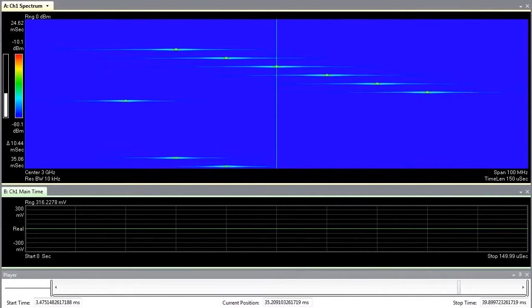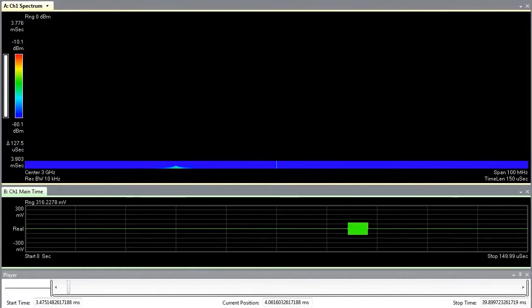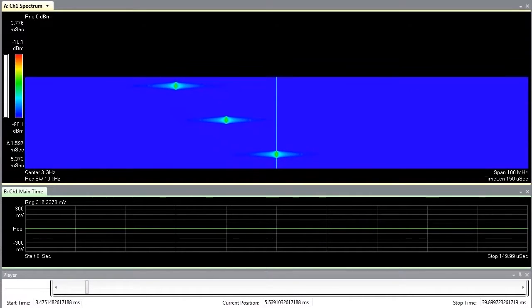Triggered time capture is especially powerful for agile signals and complex signal environments. Adjustable playback speed and advanced display types make the VSA a great complement to real-time spectrum.